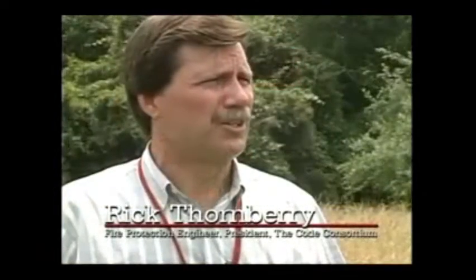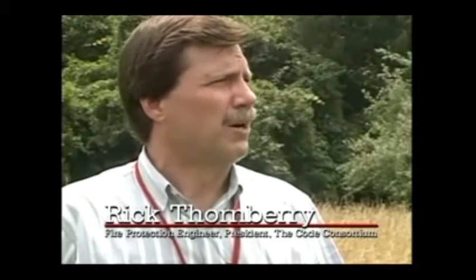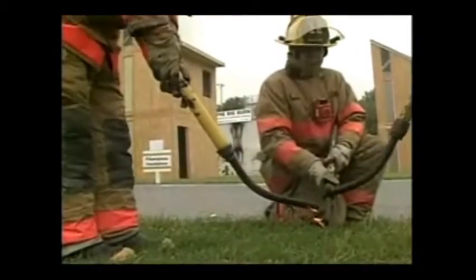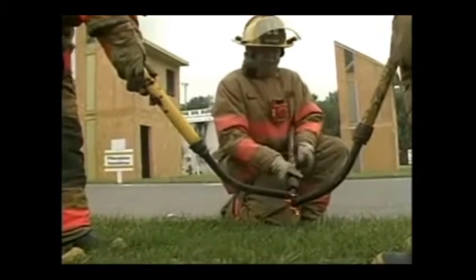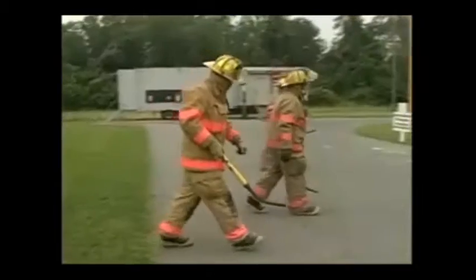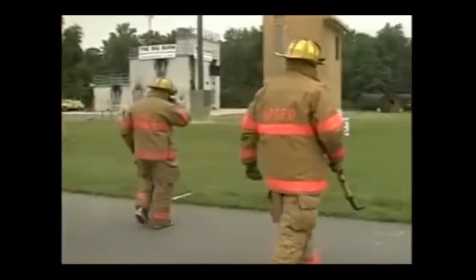The purpose of the demonstration was to compare the fire performance of 3 buildings, one uninsulated, 2 insulated, one insulation being fiberglass, and the other insulation being fire retardant treated cellulose. Testing the fire resistance and fire blocking qualities of a cellulose, a fiberglass, and an uninsulated home, the Big Burn validated previous laboratory test results.